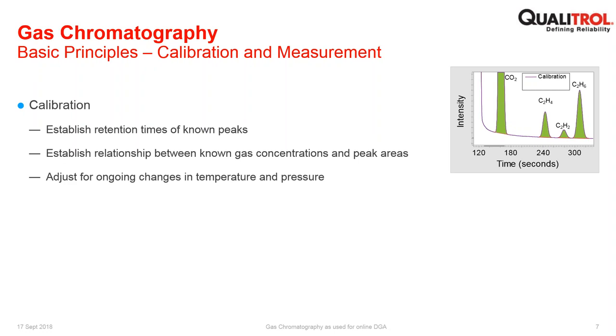And for dissolved gas analysis, we know what the gases are, right? We know that they're hydrogen, methane, ethane, ethylene, acetylene, carbon monoxide, carbon dioxide, oxygen, and nitrogen. And that doesn't change. There are additional gases in the oil, but those are the diagnostic gases, or the key gases. So you establish a retention time of known peaks for those 9 gases, establish a relationship between known gas concentration and the peak area.